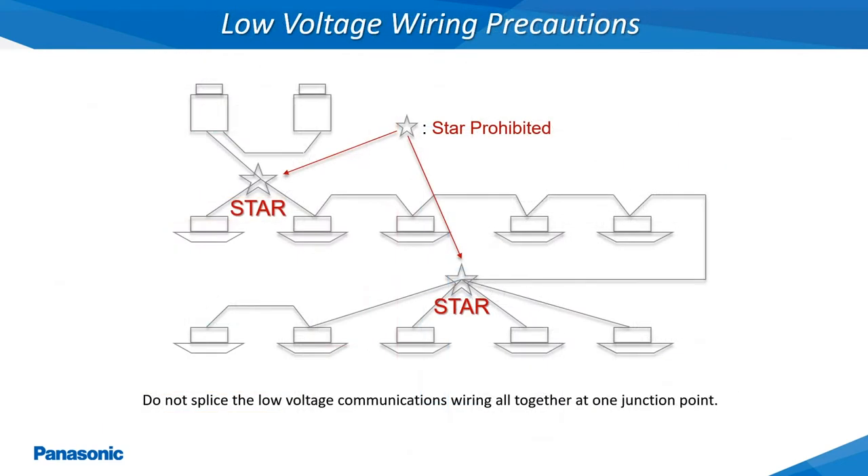The low voltage communications wiring is a very critical part of the ECOi VRF systems. This communications wiring must be installed only in a daisy chain configuration. This slide illustrates one of the common mistakes where the wiring was starred together at one or more junction points. This type of wiring configuration will cause communication errors to occur and should not be installed as shown.